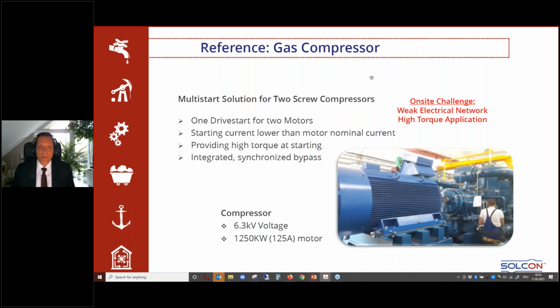Another application was for screw compressors. Screw compressors do have constant torque. In this case, it was multi-start: one drive start for two motors, starting current lower than nominal motor current, high torque at starting. You remember the constant torque, synchronized bypass, 125 amp motor.